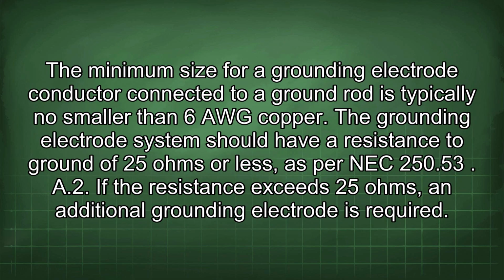The minimum size for a grounding electrode conductor connected to a ground rod is typically no smaller than 6 AWG copper. The grounding electrode system should have a resistance to ground of 25 ohms or less, as per NEC 250.53. A2. If the resistance exceeds 25 ohms, an additional grounding electrode is required.